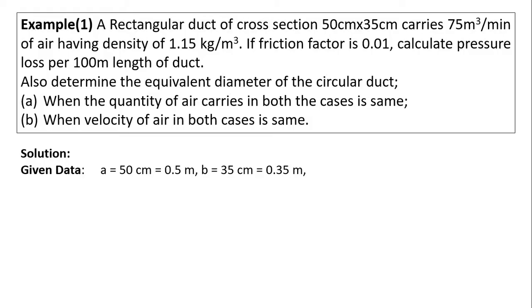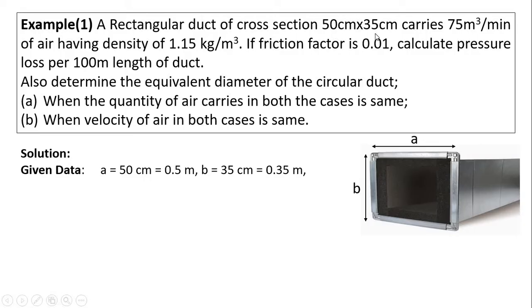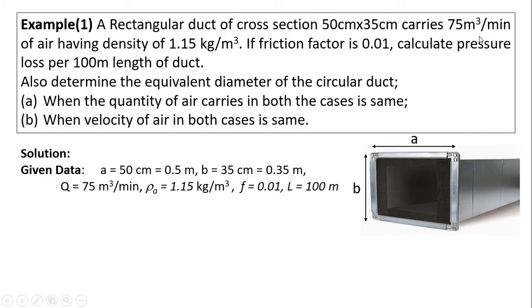First we will write the given data. The rectangular duct has larger dimension a = 50 cm = 0.5 m and shorter dimension b = 35 cm = 0.35 m. Volume flow rate of air through the duct is Q = 75 m³/min. Density of air rho = 1.15 kg/m³. Friction factor f = 0.01 and the length of duct is 100 m.